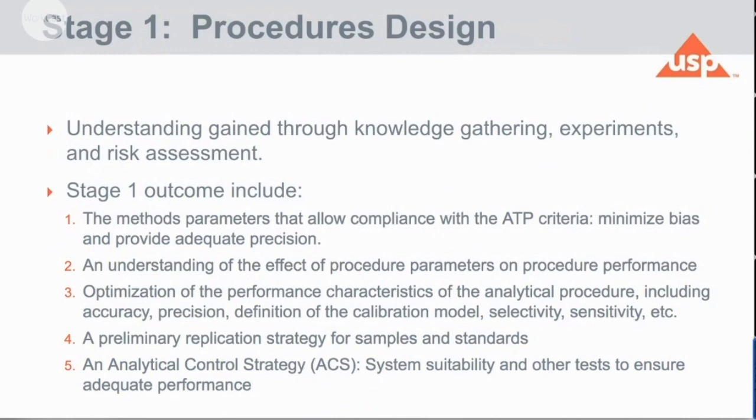We optimize the performance characteristics of the analytical procedure, including accuracy, precision, definition of the calibration model, selectivity, sensitivity, etc. We define a preliminary scheme for replication strategy, how many samples, how many standards we need to run every time that we run the test.